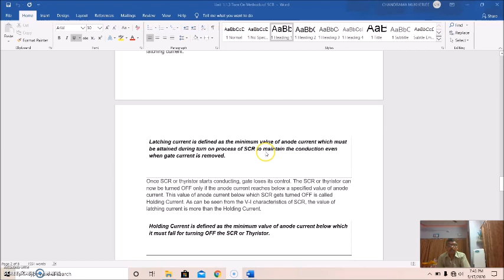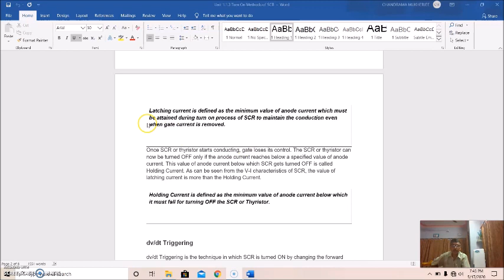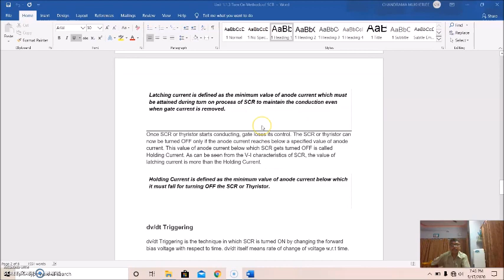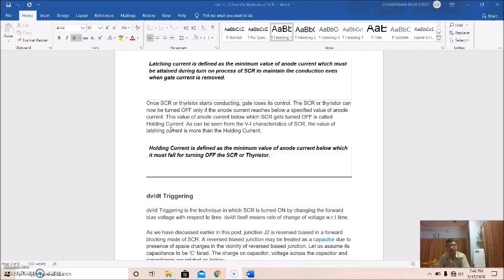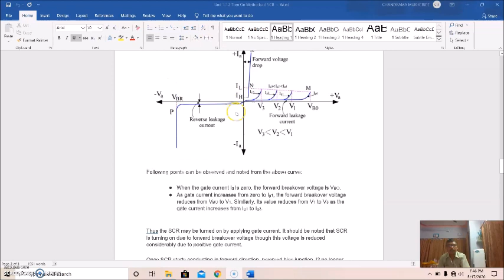Latching current can be defined as the minimum value of the anode current which must be attained during the turn-on process of the SCR to maintain conduction even when the gate current is removed. So unless the anode current reaches this latching current value, you can't remove the gate current. Once the thyristor starts conducting, the gate loses its control. The SCR or thyristor can now turn off only if the anode current falls below a specific value, and unless it is reduced to this particular value, the conduction of the thyristor will not stop.